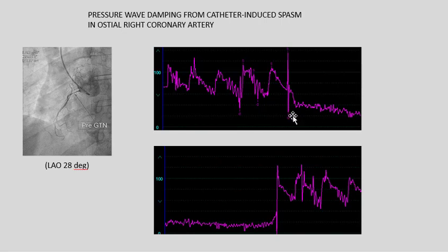And that's an expression of damping. Anything that interferes with the transmission of the natural energy of a pressure waveform is called damping. It obliterates that pressure trace. We don't know the cause of that necessarily unless you were watching that.